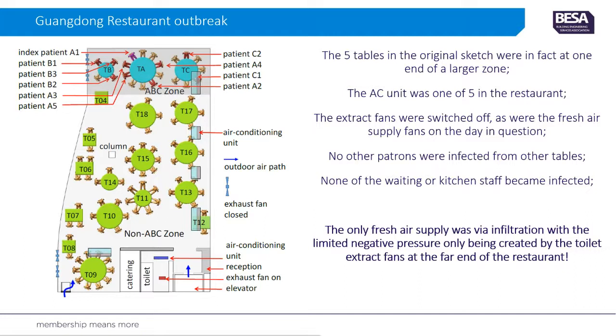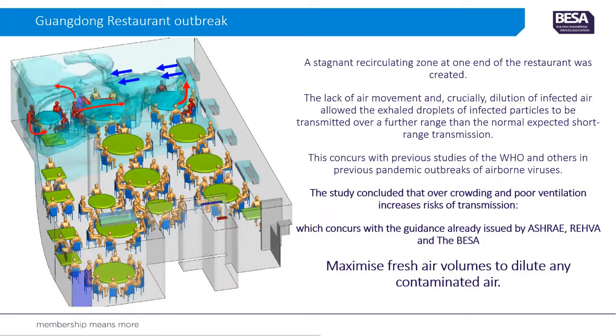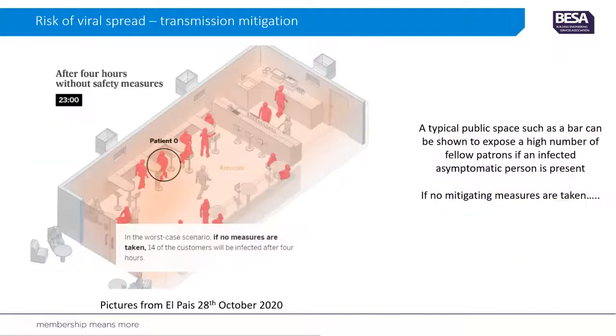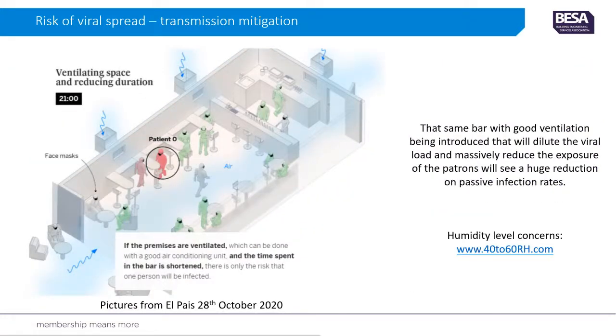It turned out that the occupation density in the restaurant was 1.55 square meters per patron, which is laughably low. It was Chinese New Year's Eve, and it packed extra tables in to try and maximize profits, but it actually meant, with that lack of air supply, that the air supply was only 1 litre per second per person in the restaurant as well, which is quite worrying. But I'm going to skip over this to try and get to what we've actually been doing about it. And if anyone wants me to go back on some of this stuff afterwards, I'm quite happy to do it separately and take it up.